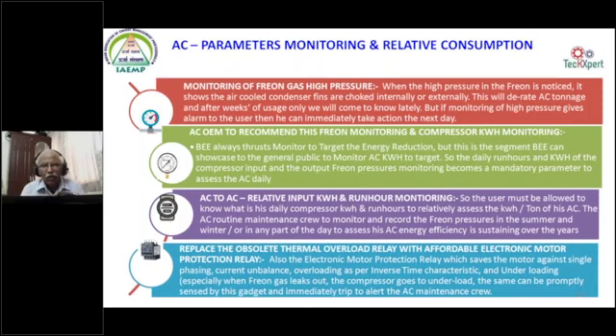Here you can put electronic motor protection relays with underload protection. Once the freon gas has leaked out and the suction pressure is dropping, let us say, from 50 psi or 60 psi to 35 psi, it can give an alarm. Inferential gauges are there on the electronic side. We can put it on the motor panel, and still you can know the freon compressor is going for underload because of low gas. This can also be checked.